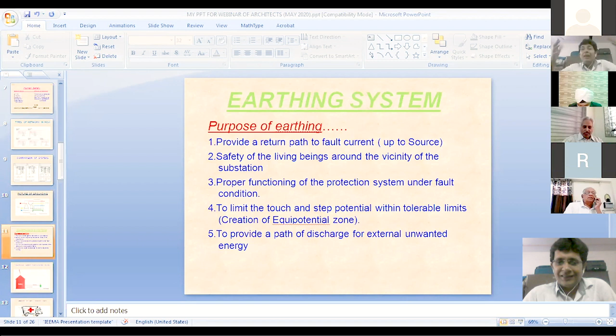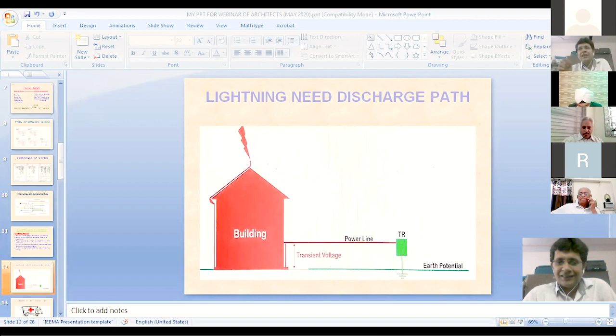You have to limit touch and step potential. You have to provide a path for discharge current, because lightning may strike your building, and if there is no path, there is going to be disaster. Whenever lightning occurs, you need a dedicated path to discharge that current to earth, and that is done by earthing. Earthing means designing - it is not just inserting one rod into the motherland.